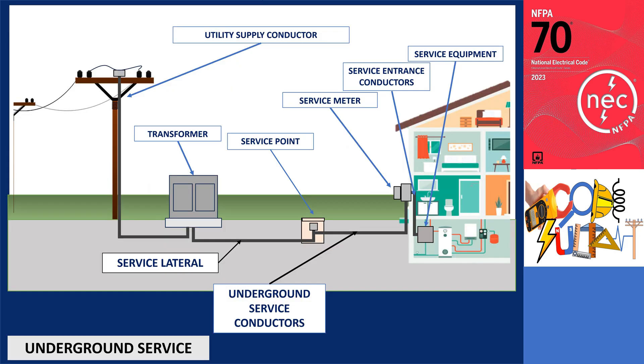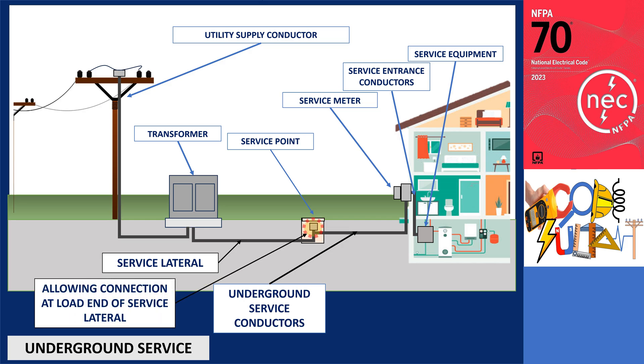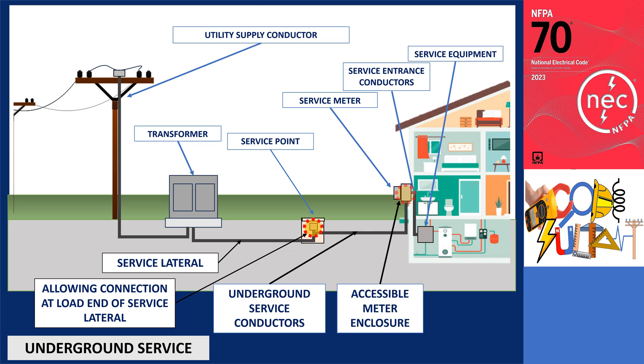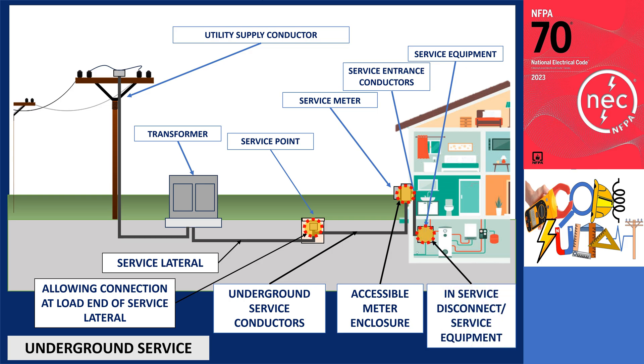In the case of an underground service, the grounding electrode conductor connection should be established starting from the load end of the service lateral or underground service conductors. Similarly to overhead services, the connection can also be made at the meter enclosure and service equipment.